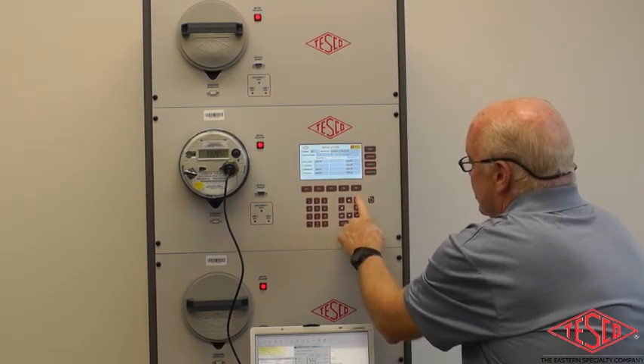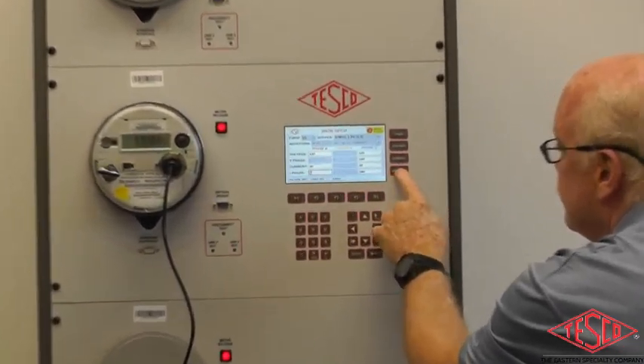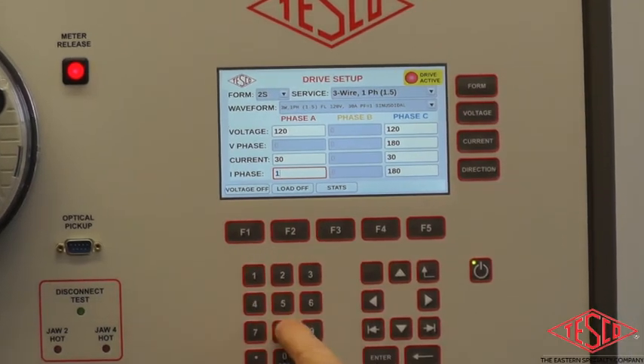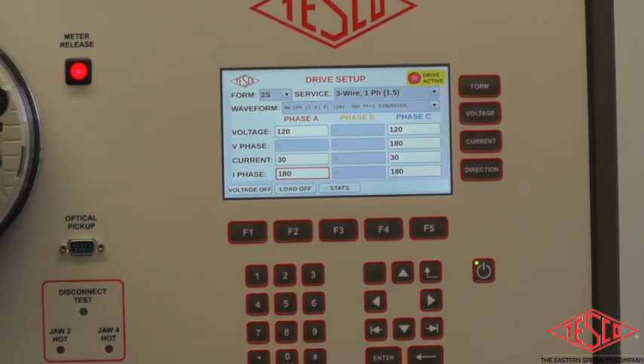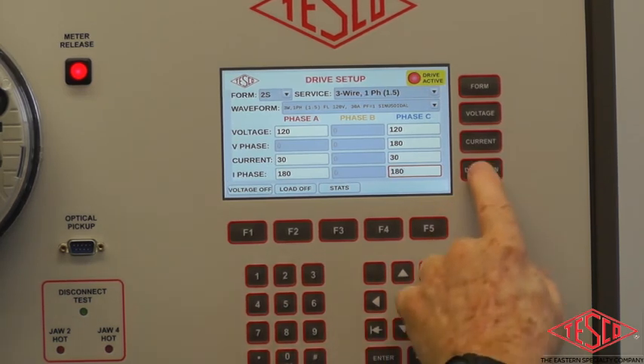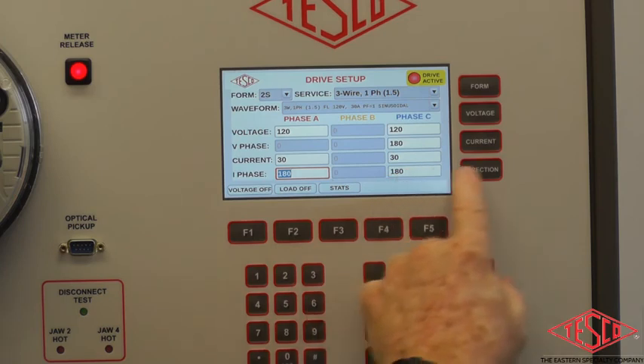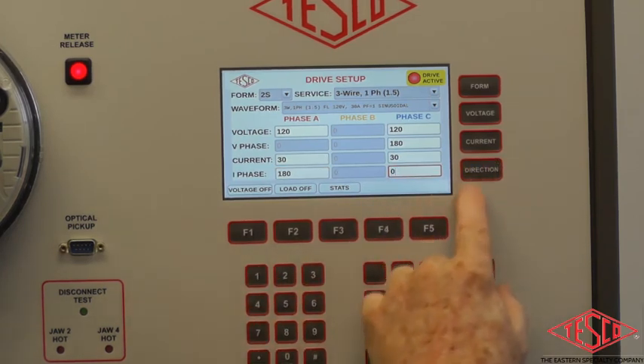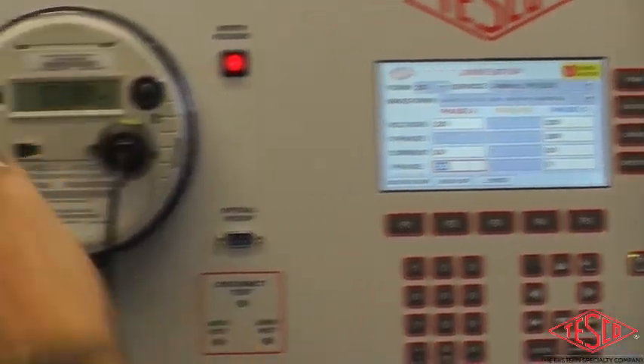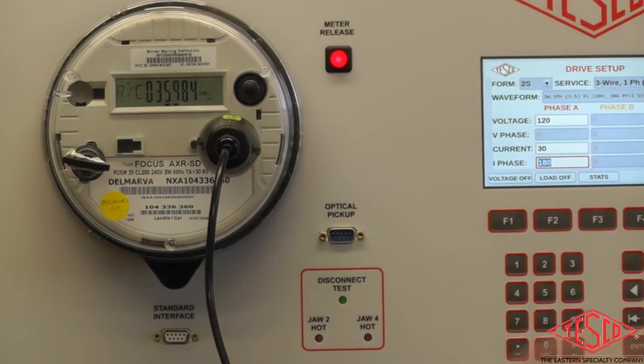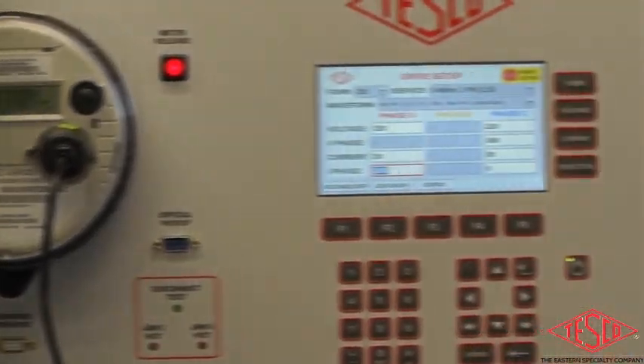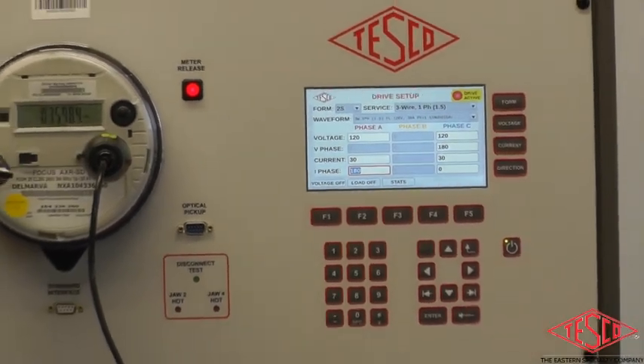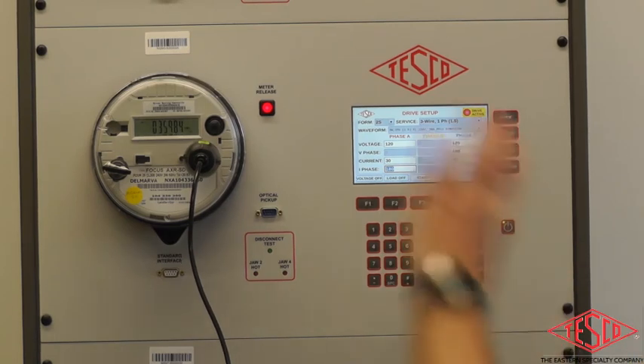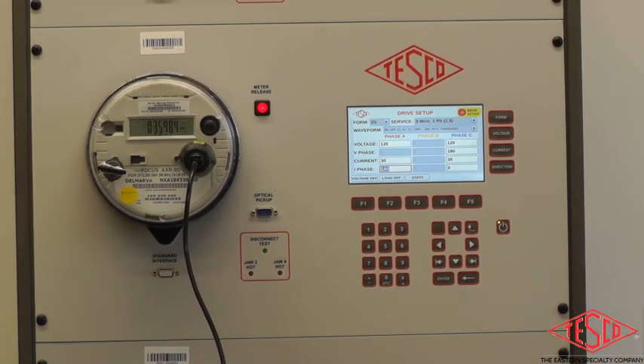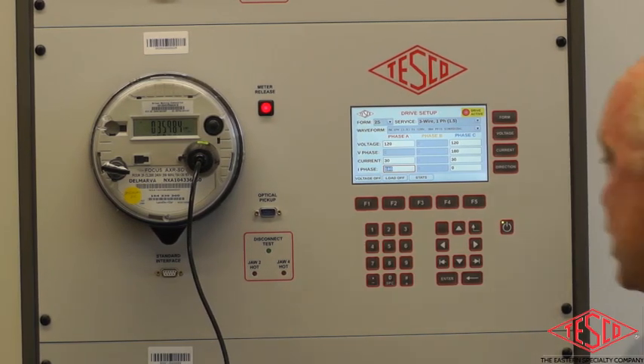Once again, you can go back to these functions here. So we go back to the main screen. If we want to change direction, we can change the direction of a phase to 180 on here. And 180 and 0, 180 here. Now we'll be able to see that the meter is going backwards. We've changed direction of both of the phases. So you can control each phase individually. You can change the various phase angles. You can change the direction. You can change the voltage. So you can basically change every aspect of the meter power parameters through the screen.